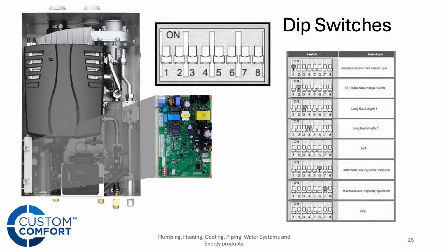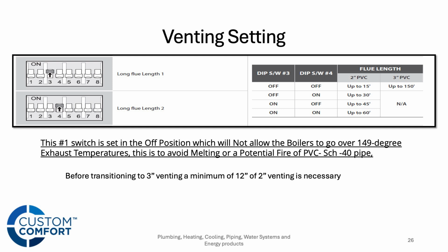Continuing on, things to look for when setting up the boiler are the dip switches located on the control board. When you're facing these boilers, the bottom left of the control board is where you're going to find the dip switches. That becomes important when you're setting up the vent parameters. We're just going to tell the boiler how far we're venting. When we talk about venting, it's 2-inch venting off the top. If we're venting in 2-inch, we're good up to 60 feet.